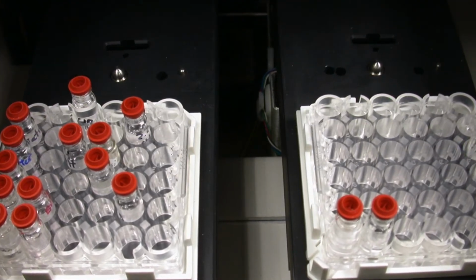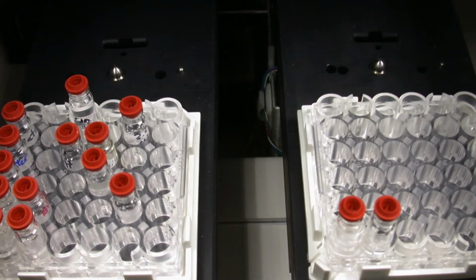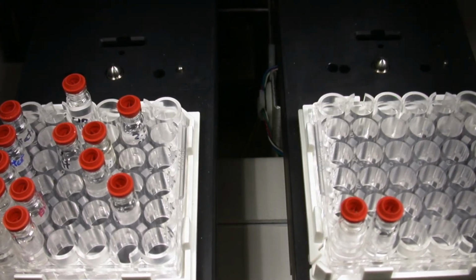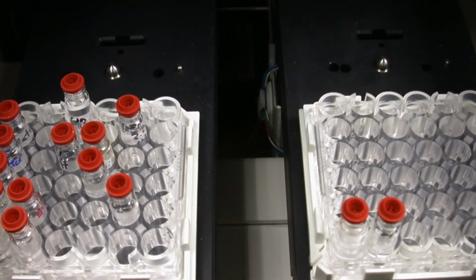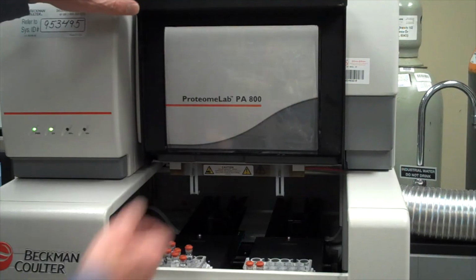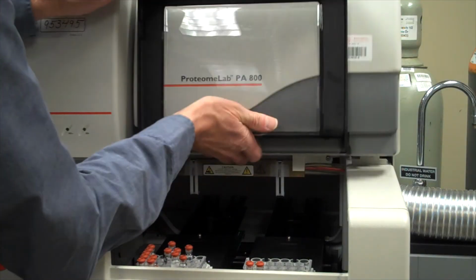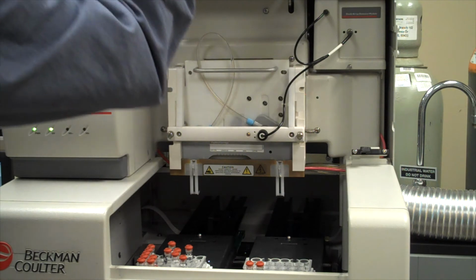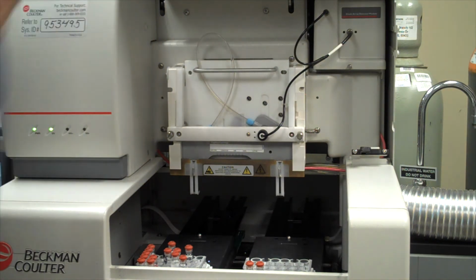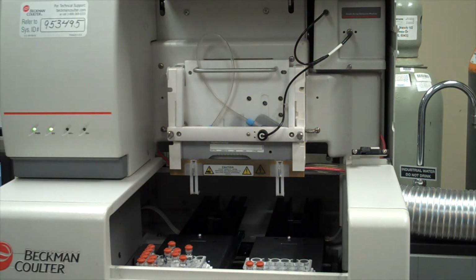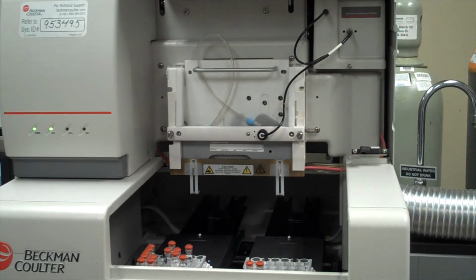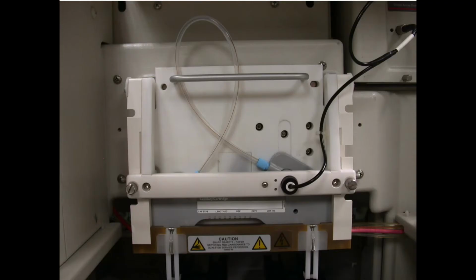The tray on the right holds the vial for the running buffer, and usually a vial that collects the rinse solution that is introduced on the opposite side of the capillary. The second door can be opened by pulling outward where the first door was hinged. This reveals the capillary that is housed in a plastic tube. This clear tube contains a cooling fluid that helps maintain the temperature of the separation capillary.